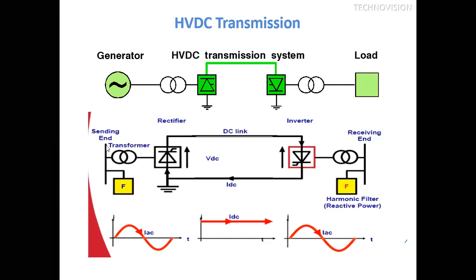Here, if you see, this is the sending end and this is the receiving end. And here in the AC side, you have to connect the filters. In the conventional technology, that is, we can say, line commutated converters or thyristor based technology, you have to connect these filters to the AC side as well as the DC side. And here AC is converted into DC, and again DC is converted into AC. If you see here, current is actually converted. Current is converted in AC to DC, DC to AC. So that's why thyristors are known as current source converters.